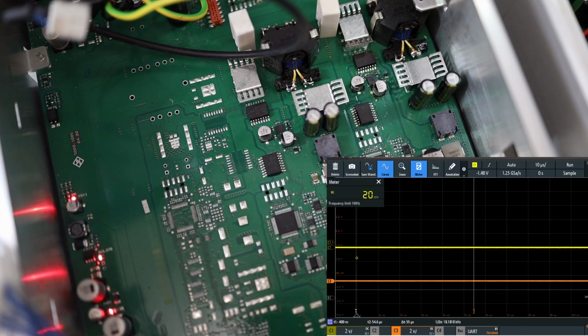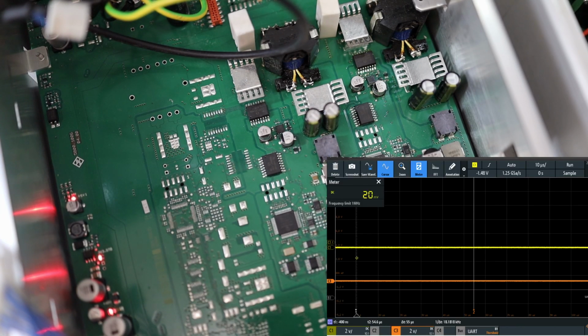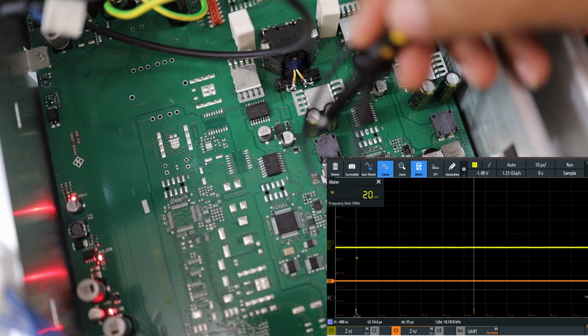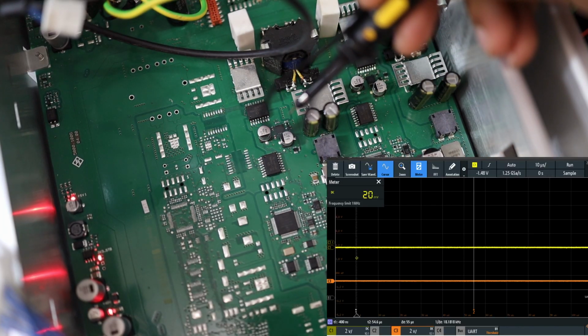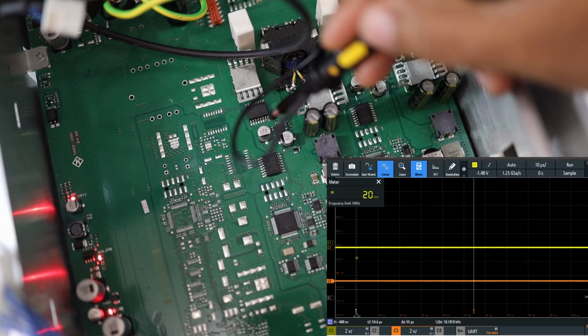So we will measure. We will flip the instrument. We will measure on the fuse itself to see if it is getting power. If it is not getting power, these things need a dedicated 3.3 volt supply, isolated from one another and from the whole instrument, to be able to function. And if this 3.3 is not coming, you will not see any activity.